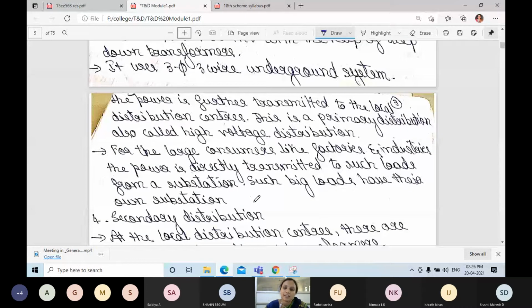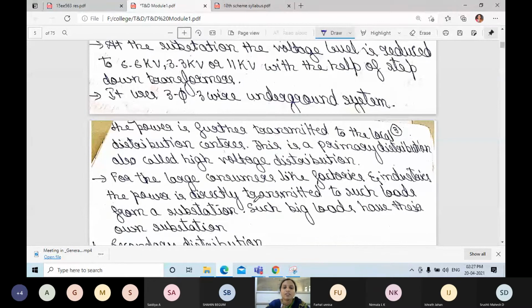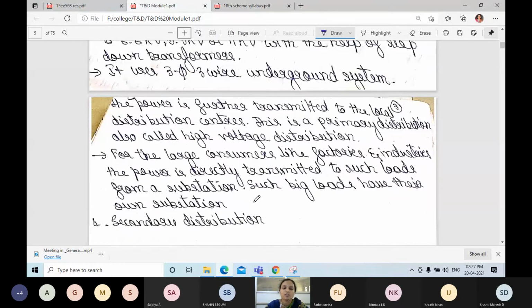Power is further transmitted to the local distribution centers. This is a primary distribution, also called high voltage distribution. Next, for the large consumers like factories and industries, the power is directly transmitted to such loads from a substation, because here the load is 3.3 kV or 6.6 kV, it may be 11 kV. So again, it can be supplied to factories and industries. The power is directly transmitted to such loads.